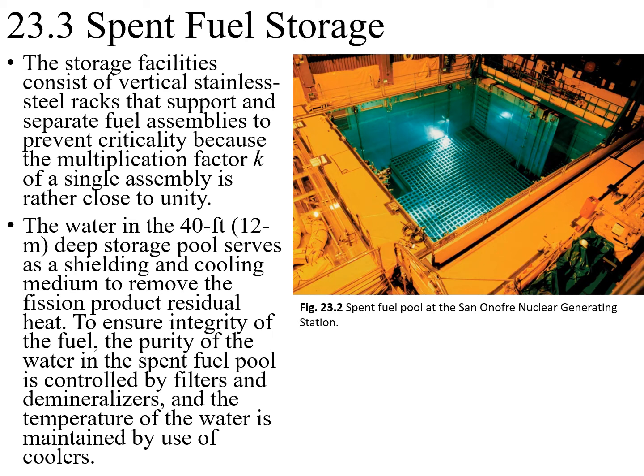The water in the 40-foot-deep storage pool serves as the shielding and cooling medium to remove the fission product residual heat. To ensure the integrity of the fuel, the purity of the water in the spent fuel pool is controlled by filters and demineralizers, and the temperature of the water is maintained by coolers.